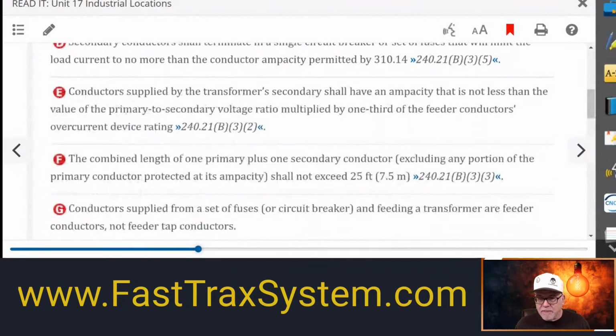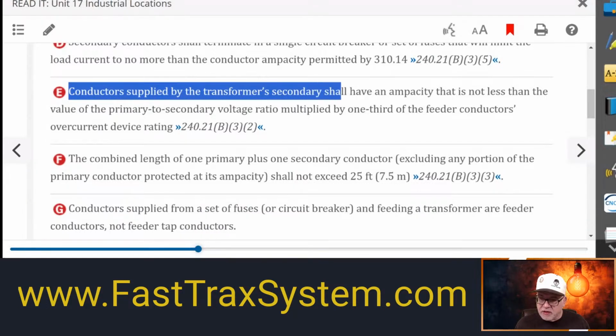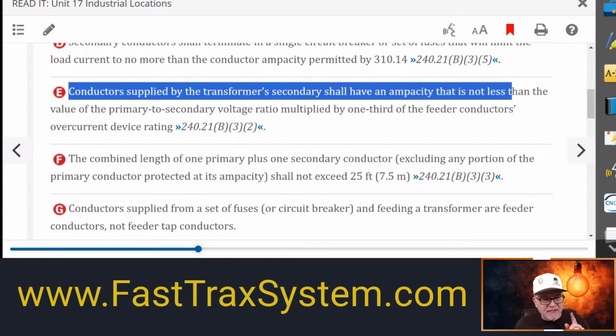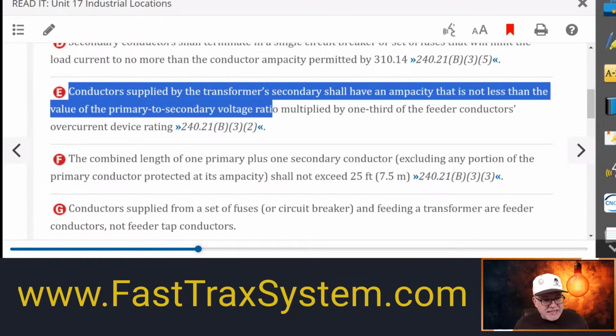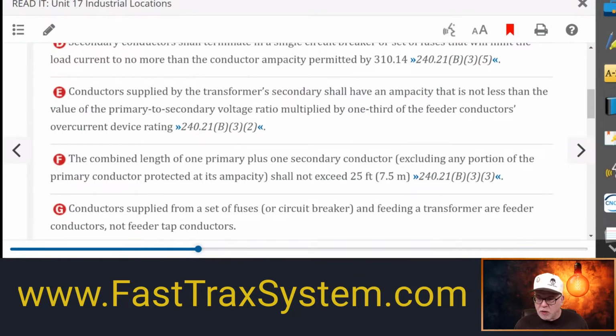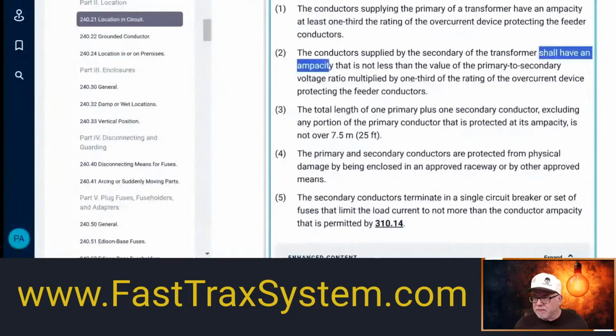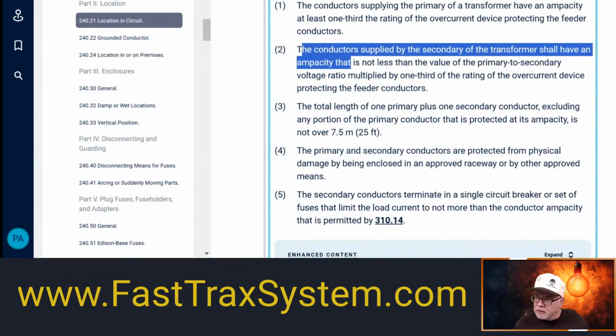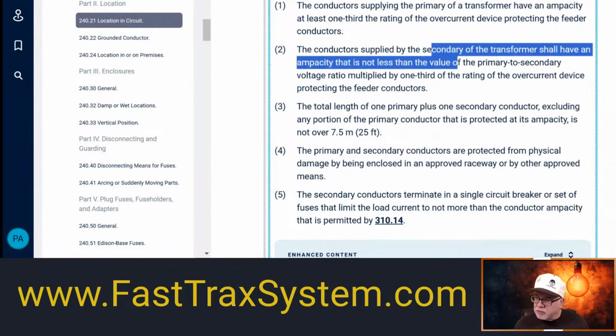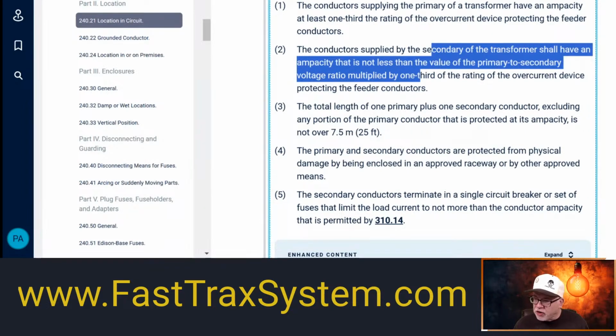And as you can see in your call out, it says the conductor supplied by the transformer secondary shall have an ampacity of not less than, could be more, not less than the primary to secondary voltage ratio, which we did, multiplied by 1/3 of the feeder conductor's overcurrent device rating. Okay, so that's what we have in 240.21(B)(3)(2). So let's go back to the code. And again, the conductors supplied by the secondary of the transformer shall have an ampacity of not less than the value of the primary to secondary voltage ratio, which is 2.31, multiplied by 1/3 of the rating of the overcurrent device protecting the feeder conductor.